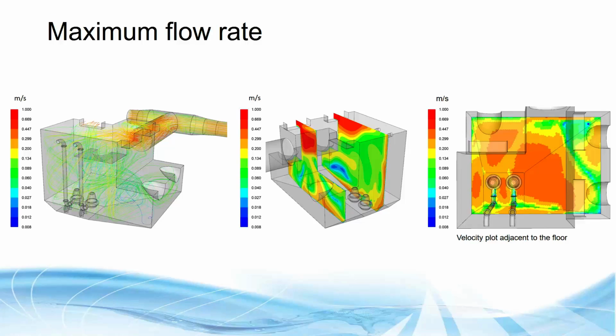As you can see from the last plot as well, there were velocities from the cells close to the floor, but these recirculation zones formed where velocities weren't high enough, and this would cause issues where the floc could start to settle and would then be re-picked up by the high velocities and recirculated. That could extend residency time within the chamber itself and then not leave, then be transported to final settlement tanks.